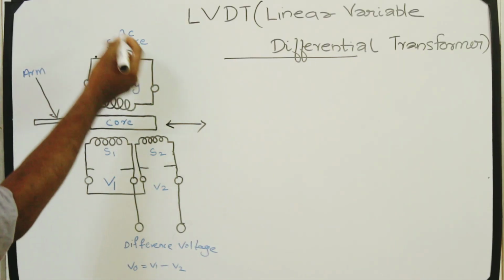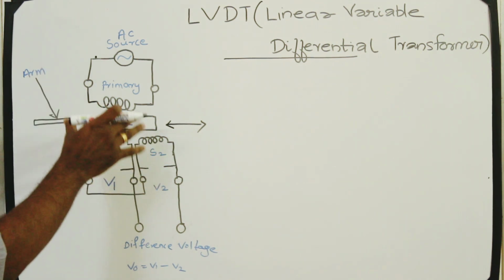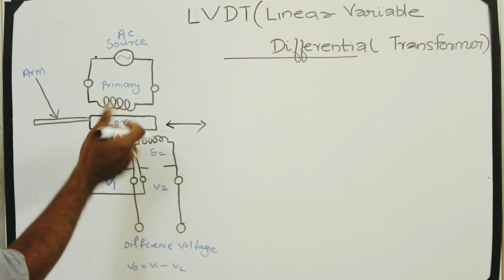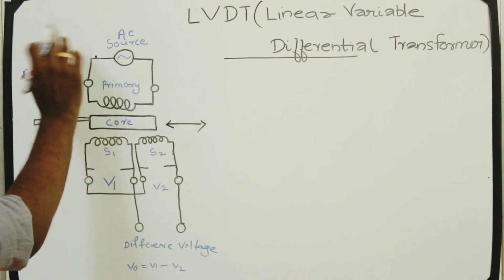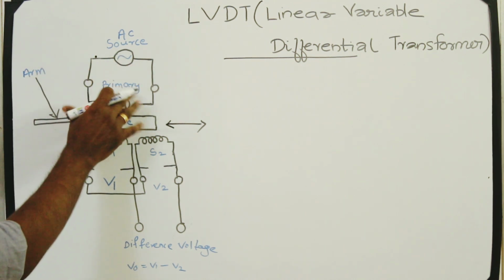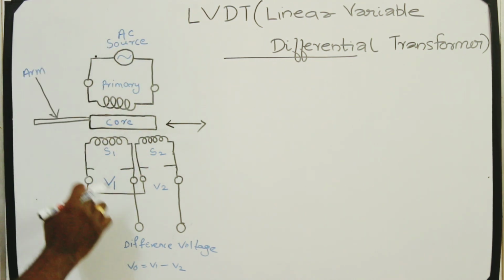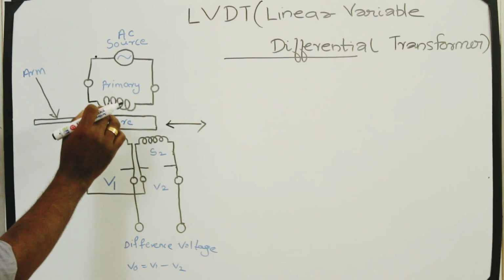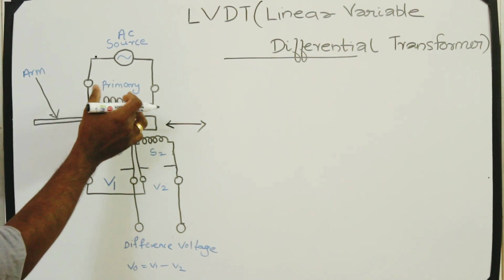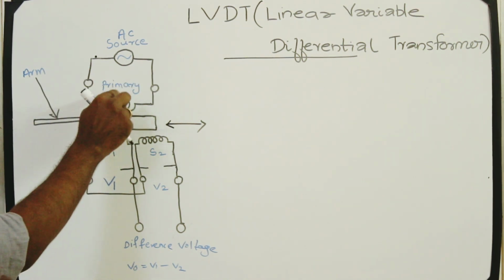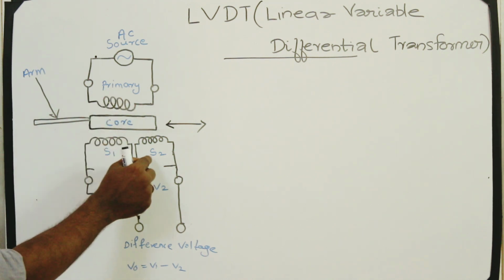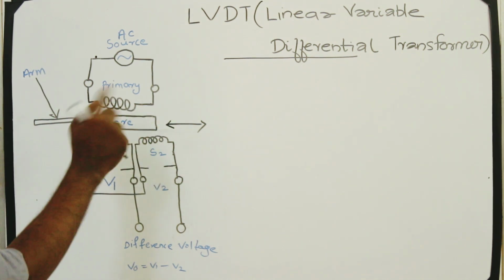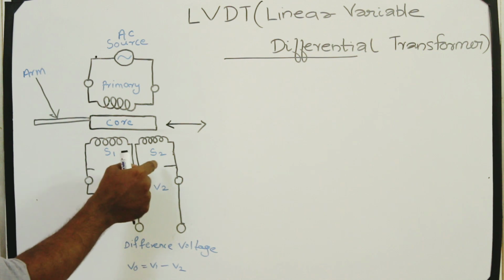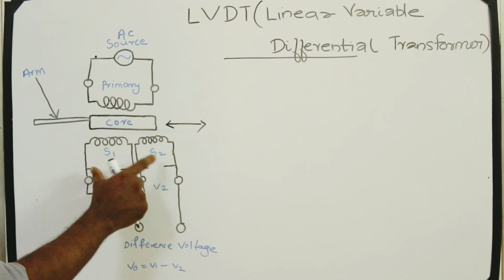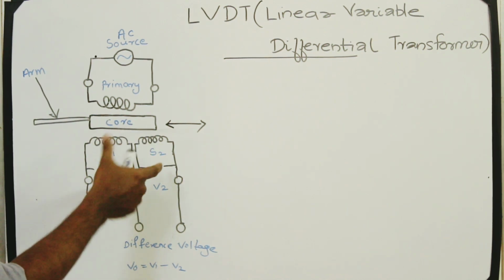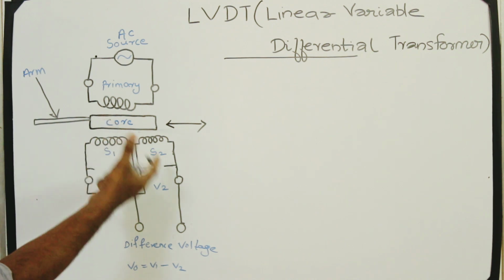So, this is the diagram of an LVDT, linear variable differential transformer. The main components of an LVDT are a transformer and a core. The transformer consists of three coils, a primary and two secondaries, S1 and S2, wound on a hollow form which is typically made of glass reinforced polymer.